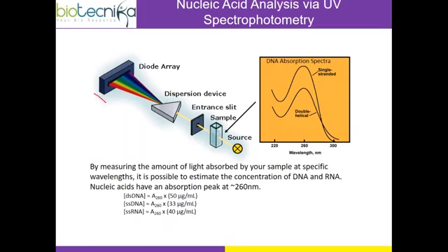Sorry guys, I am explaining in the wrong way. It should be like, this is a light source. It will hit the prism, monochromator prism. Here you see polychromatic light, from here a monochromatic light comes based on the nanometer we set, and then to enter the slit, it hits the sample and then it will be detected by my detector. So this is a specific setup of a spectrophotometer, right?